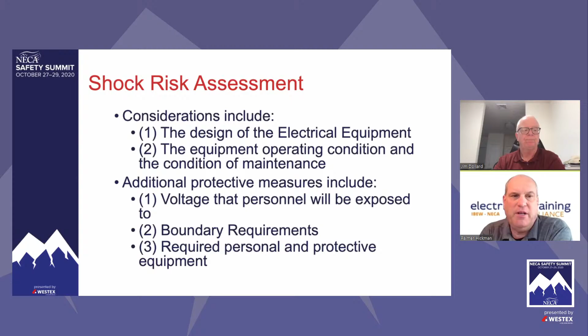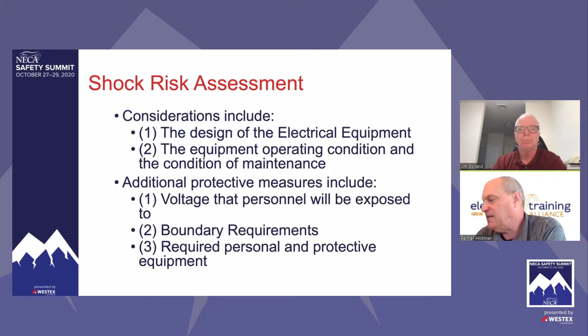But when we're doing those risk assessments, we look at the design of the equipment. We also look at the operating condition and the condition of maintenance. And additional protective measures would include the voltage that we're going to be exposed to, the boundary requirements, and any required personal protection. Let me make a quick point here if you back up. Everything Jim's talked about to this point is shock risk assessment, and we want to estimate the likelihood of it occurring. Well, we do have Table 130.5(C), estimate the likelihood of arc flash occurrence, but we cannot use that table for doing our shock risk assessment. So that might be potentially confusing to you. Table 130.5(C), Jim's going to get into it next. Estimate of likelihood of occurrence of an arc flash incident. You cannot use it for shock.